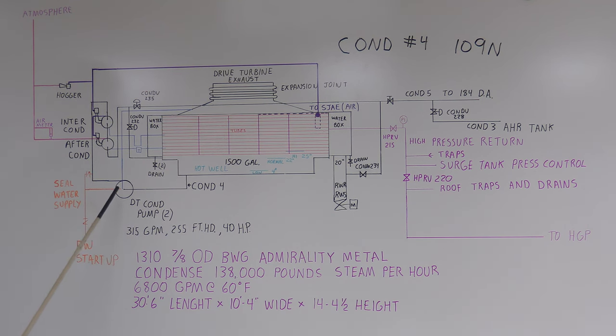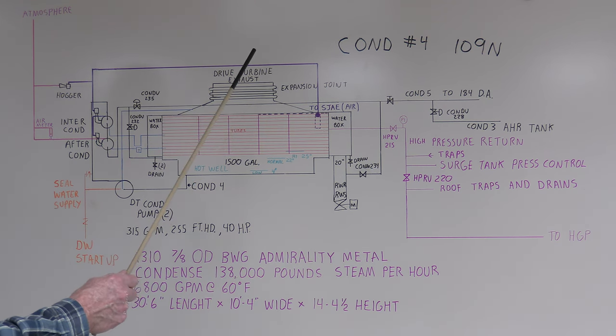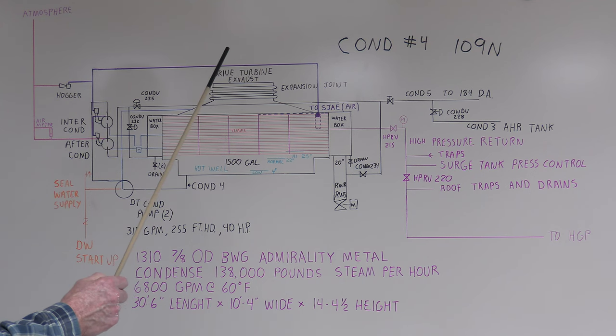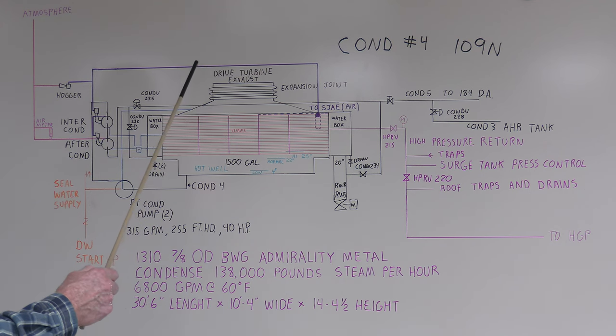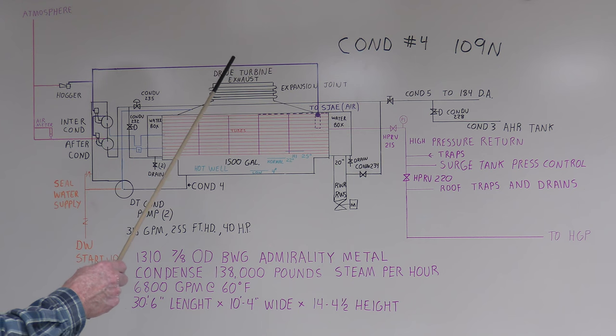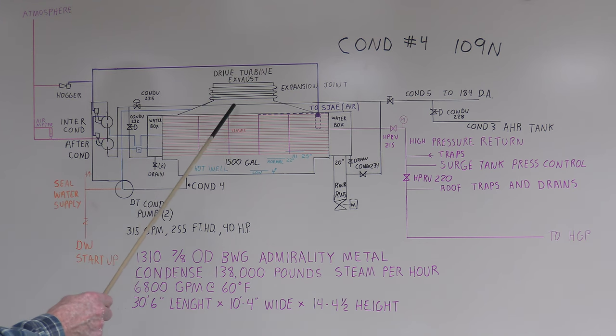We added a few more things on this. Basically, this system had your drive turbines on 109 building set up on the main floor, and down at minus 16 you had the surface condensers. The exhaust out of the drive turbines came down through an expansion joint to the top of the surface condenser.